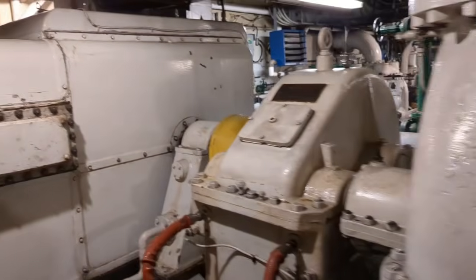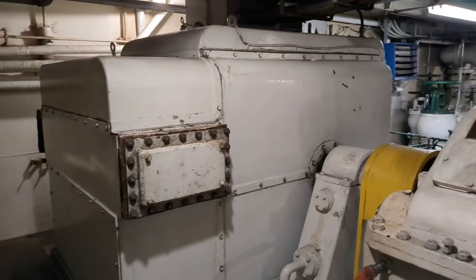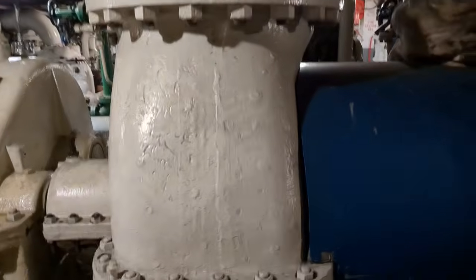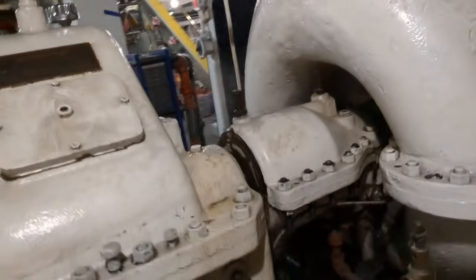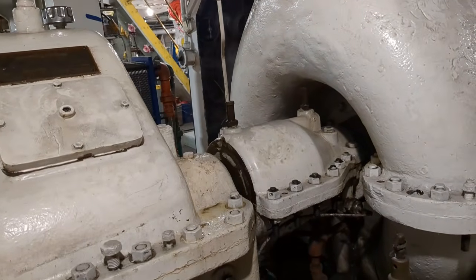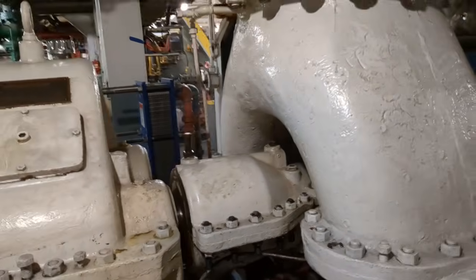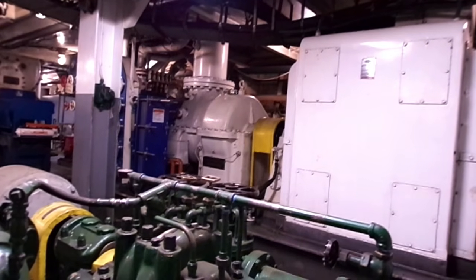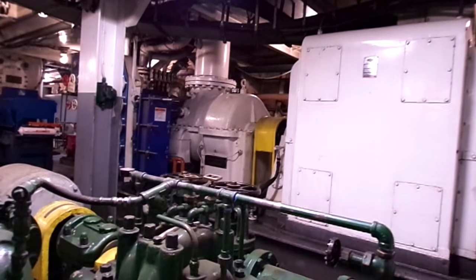These generators are driven by steam turbines through reduction gears. The turbine operates at about 6,400 RPM, while the generator turns at 1,200 RPM, producing 60 Hz power from a 6-pole alternator.